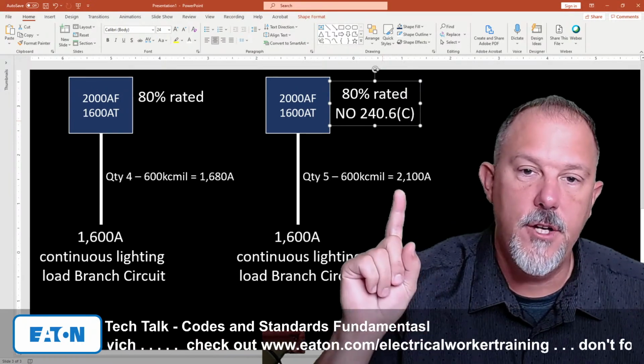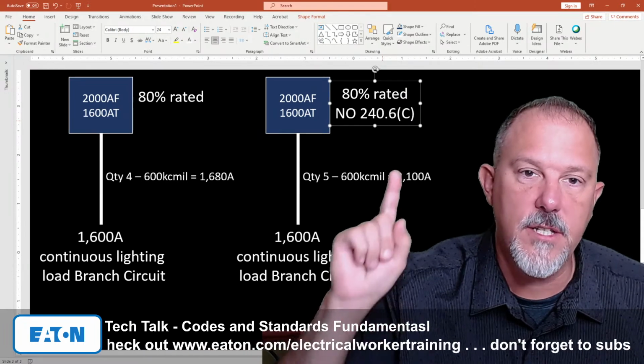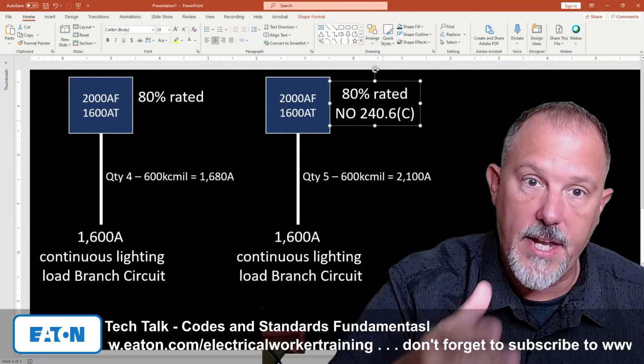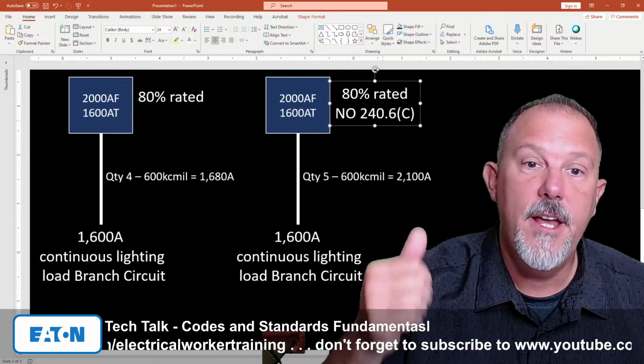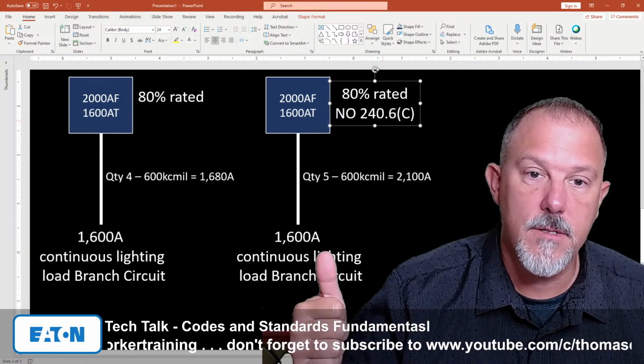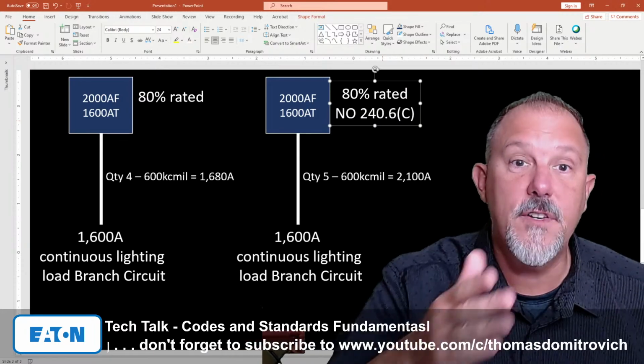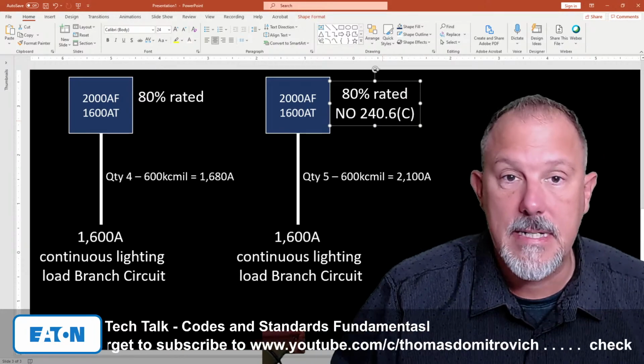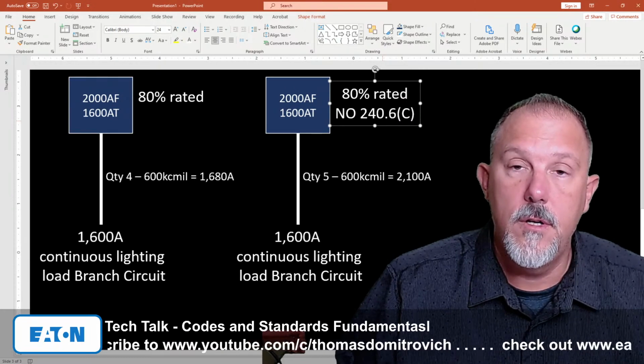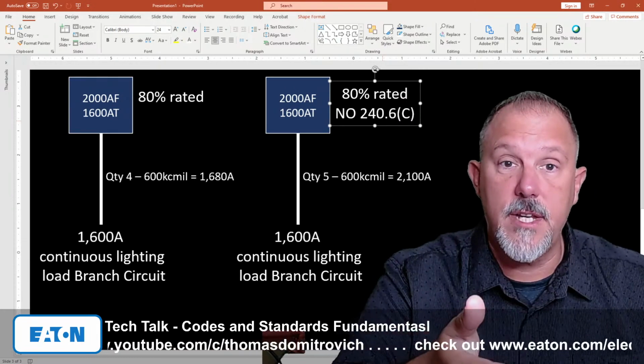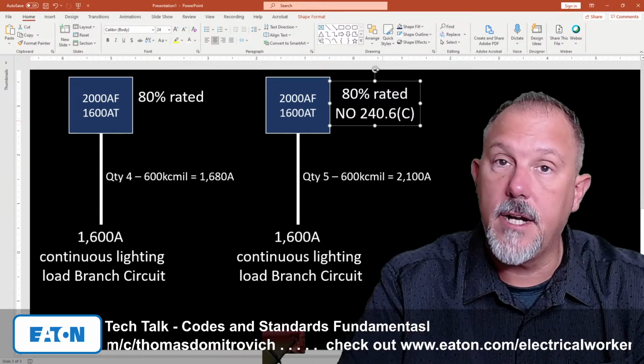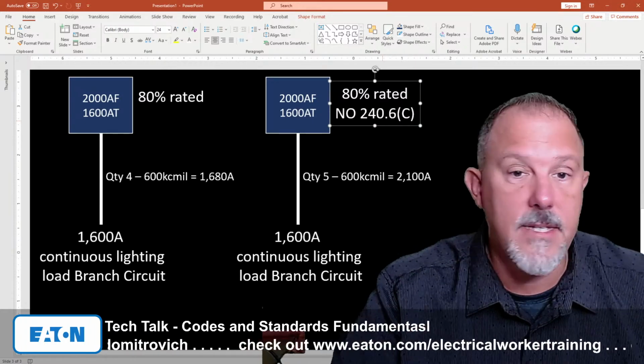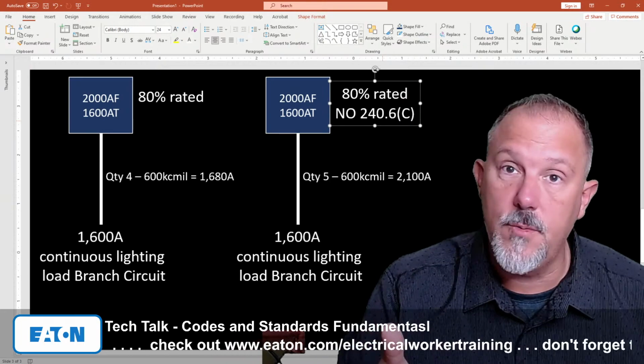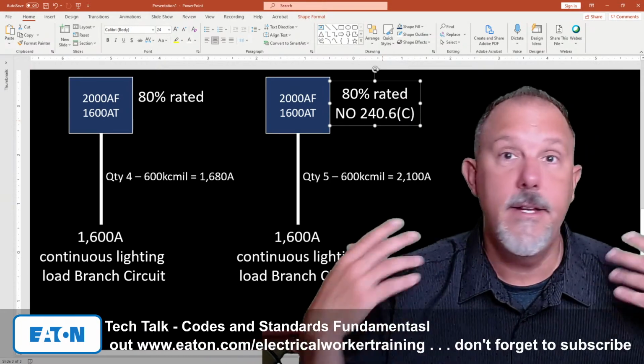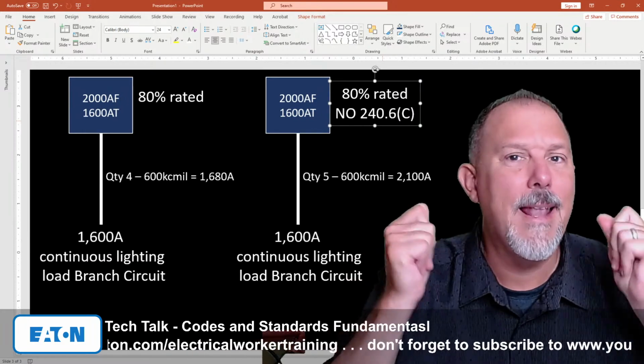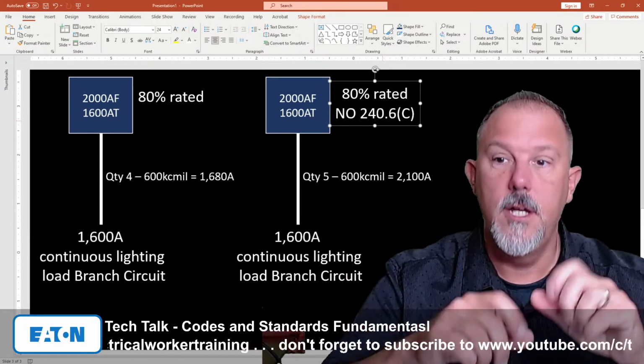I have to have 2000 amps worth of conductor because it's a 2000 amp rated circuit breaker. The rating of that breaker is 2000 amps. Then my 1600 amps is perfectly fine. I could even adjust my long time pickup down to 1600 amps if I wanted to, but I don't have to because I have 2000 amps worth of breaker and 2000 amps worth of conductor. I'm protecting the conductor at its ampacity. I'm serving 1600 amps worth of continuous load every day, all day, day and night. I don't care. Let them lights burn, brother.